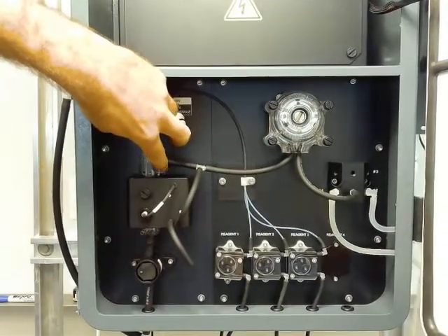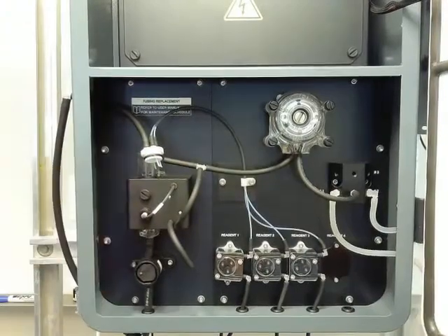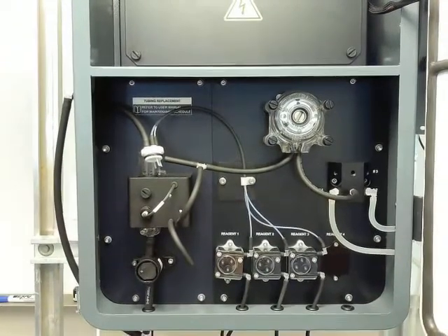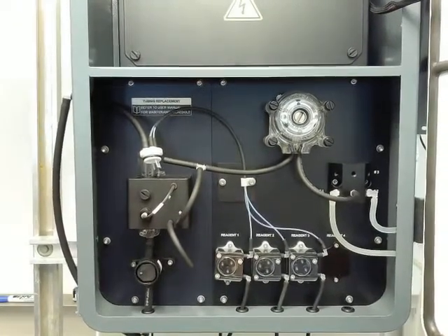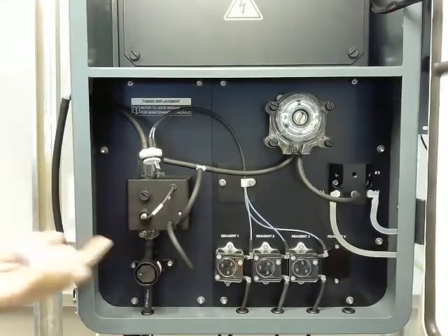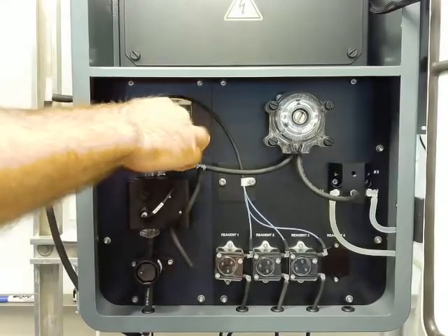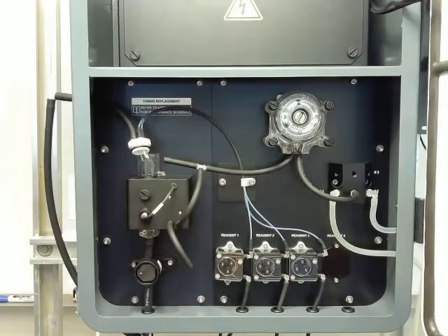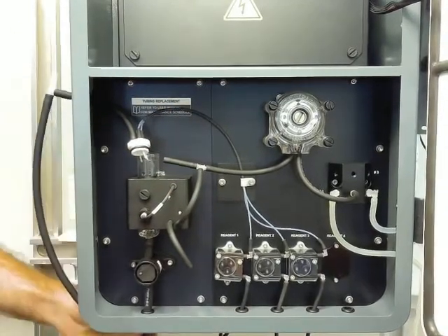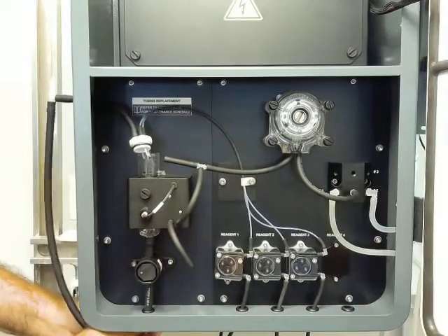Now it's very important to note that the flow cell has these inlet and outlet nipples on the top and the bottom. That's probably the most likely thing to break as you're taking this flow cell in and out. There is a groove cut in this block to rotate the flow cell when we pull it out. But before we pull it out, it's still in place. We have to release our drain tubing.